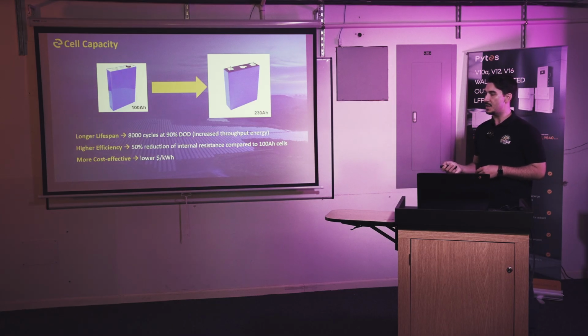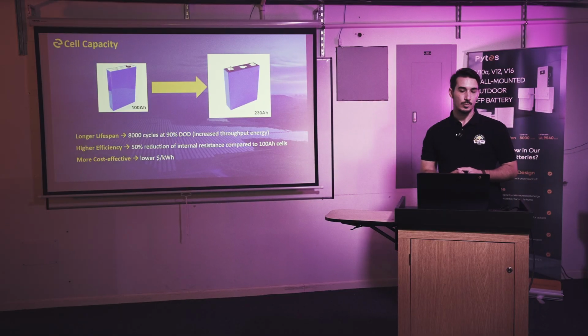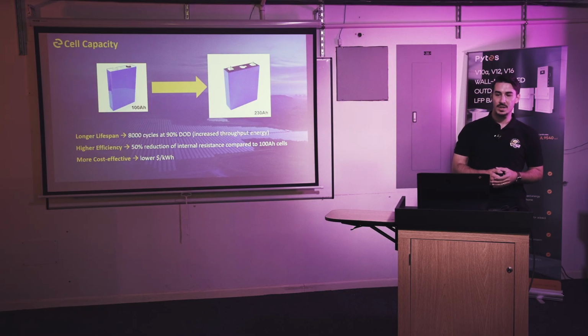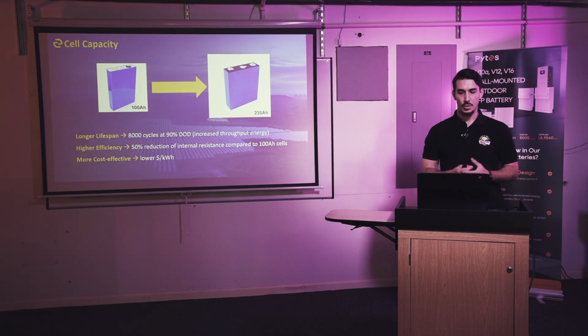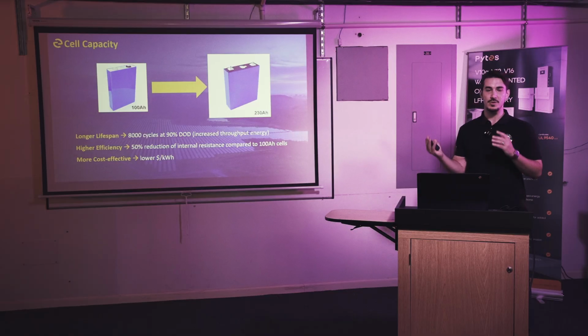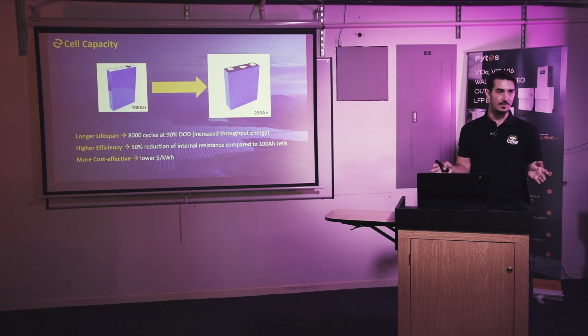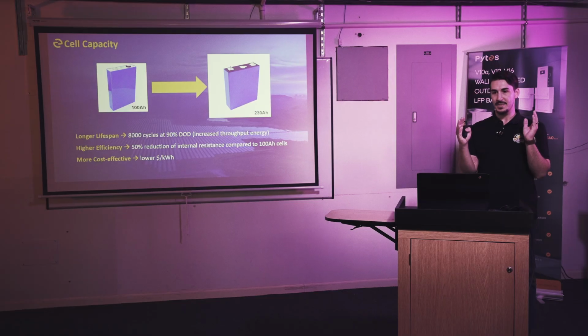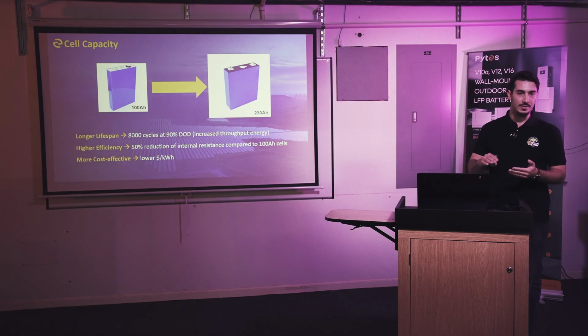You've got 8,000 cycles, up from 6,000, at the same 90% depth of discharge. I personally don't like to talk too much about cycles, because the definition isn't always consistent between manufacturers. I've heard it defined as a full charge and discharge, just a full charge, or just a full discharge. So energy throughput is a much more true way of gauging a battery's potential - it's the total amount of energy you can put into and take out of that battery throughout its entire life. We're getting rid of cycles, getting rid of time. Here's the battery, here's what you can do with it, and that's what we're backing, down to a certain capacity retention.